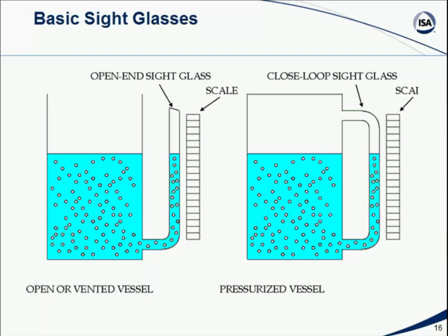And in a lot of applications such as boiler level control, sight glasses are still used, and in fact, there are technologies out there where we attach light sensors and light transmitters and clamp them on the sight glass, shall we say. We shine light through the sight glass, and if the fluid's there, the light is deflected, and if the fluid's not there, the light goes through, and we can, therefore, by looking at which sensors are detecting light, essentially read the sight glass without having to actually stand there and stare at it. So we can still make manual measurements or even automate the process by using sight glass technology.